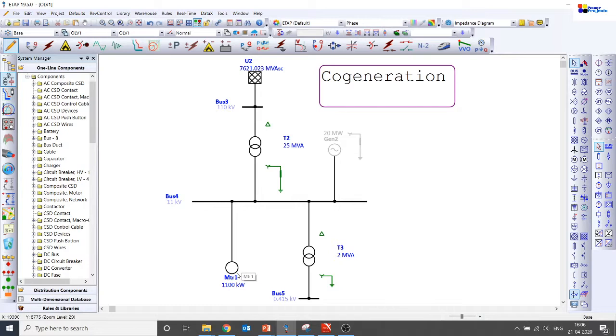To answer this: in a medium voltage system, if there are motors and a single line-to-ground fault occurs within the motor, there is a higher probability that the motor stator core gets damaged. That is the reason why it is important to limit the single line-to-ground fault current. When you have 11 kV motors, it is recommended to go with resistance earthing. This neutral grounding resistor, NGR, limits the single line-to-ground fault current well below the capability of the stator core of the motor rating.